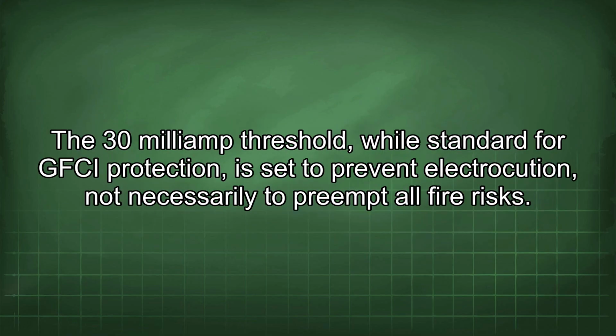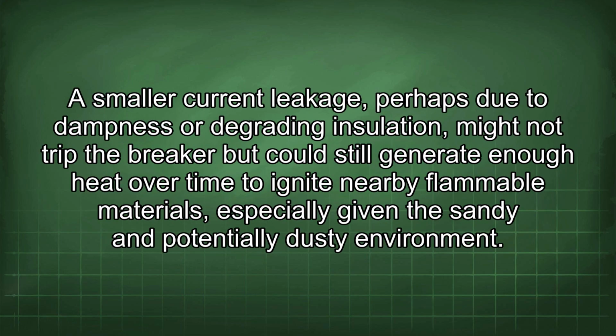The 30 mA threshold, while standard for GFCI protection, is set to prevent electrocution, not necessarily to preempt all fire risks. A smaller current leakage, perhaps due to dampness or degrading insulation, might not trip the breaker but could still generate enough heat over time to ignite nearby flammable materials, especially given the sandy and potentially dusty environment.